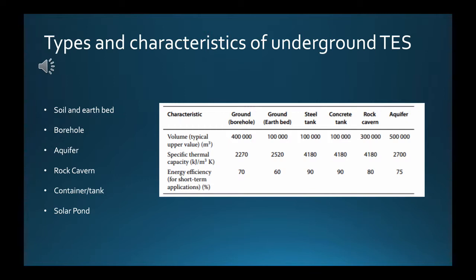An aquifer is an underground reservoir in which water is located in impermeable materials such as clay or rock and moves very slowly. An aquifer TES is typically a permeable water-bearing rock formation. Aquifers often have large volumes exceeding millions of cubic meters and consist of about 25% water. In aquifer TES, water from the aquifer is extracted and heated or cooled, then re-injected at another point in the aquifer for storage. Two well fields are often tapped: one for cold storage and the other for heat storage. Aquifer stores are most suited to high-capacity systems.